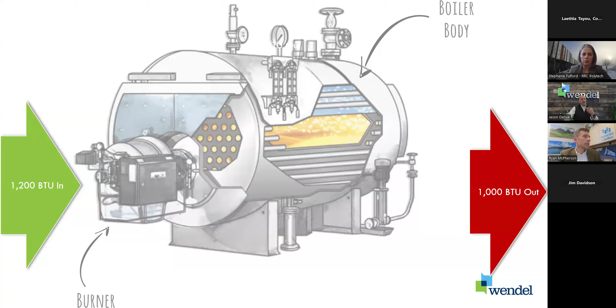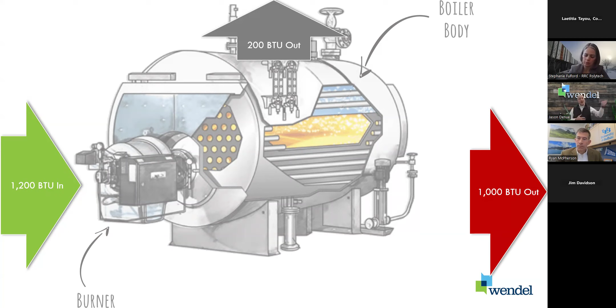So let's say you have a natural gas boiler today in most of our facilities, right? Simplifying that down a little bit, this boiler is composed of two primary spots. You have the burner and you have the boiler body. And if you wanted to get 1,000 BTUs out of that boiler, you're basically going to put 1,200 BTUs of natural gas into that boiler. About 200 of those BTUs are going to leave as waste through the flue stack. This is an 80% efficient boiler. This is what we see on the market today. This is what's in most of your facilities right now. So for the 1,000 BTUs I need to provide heat to my building, I'm going to need to bring 1,200 BTUs of natural gas in.